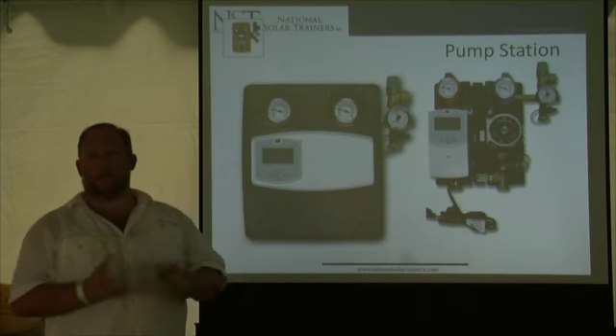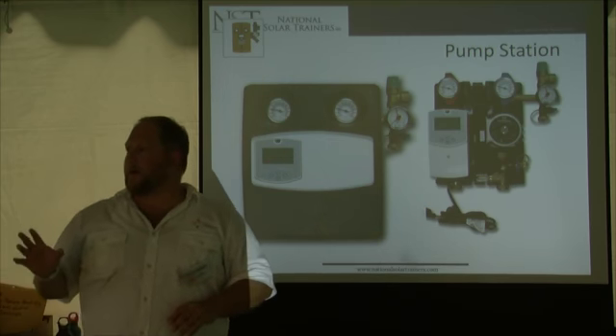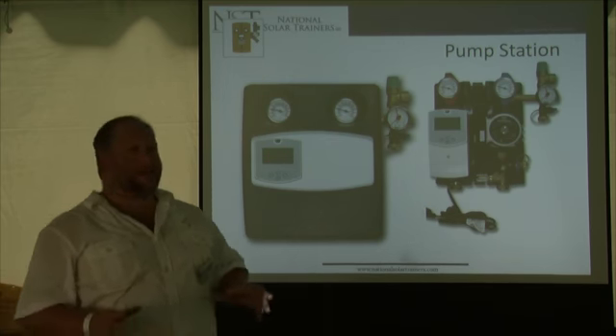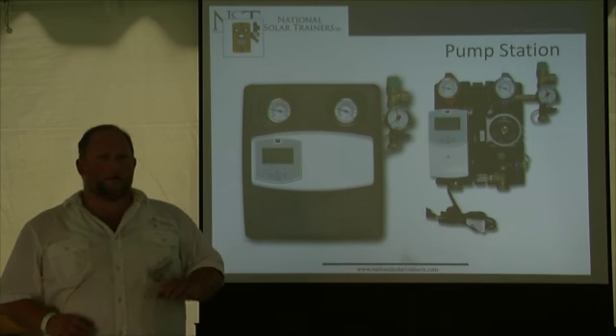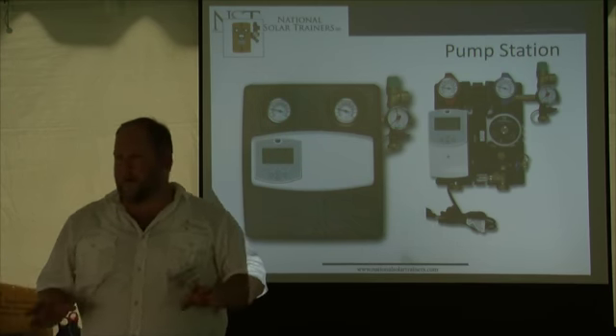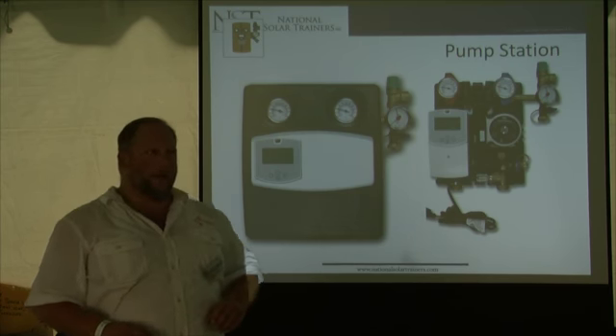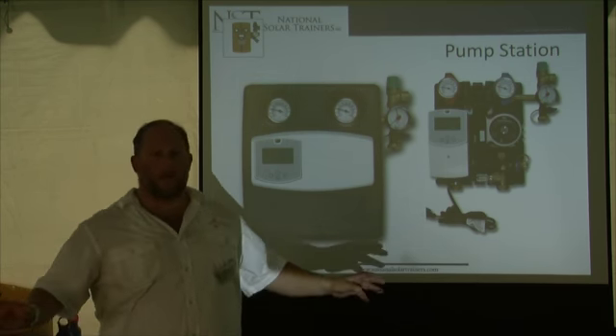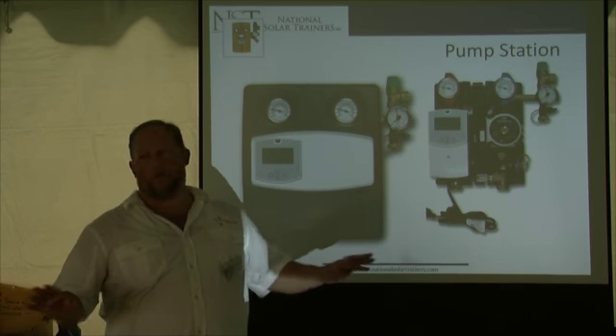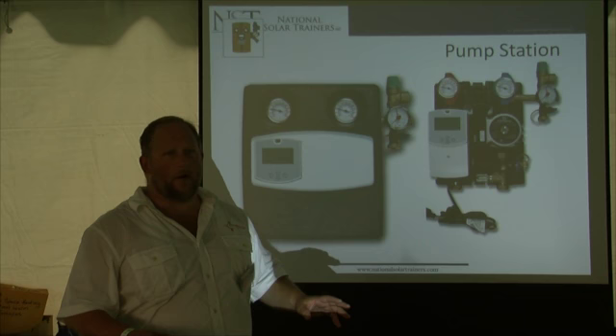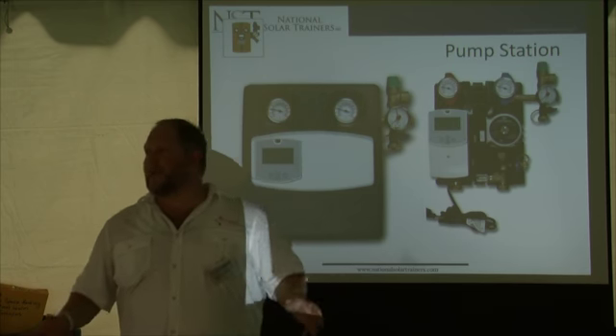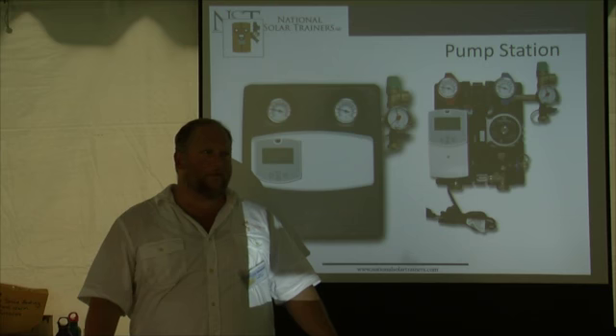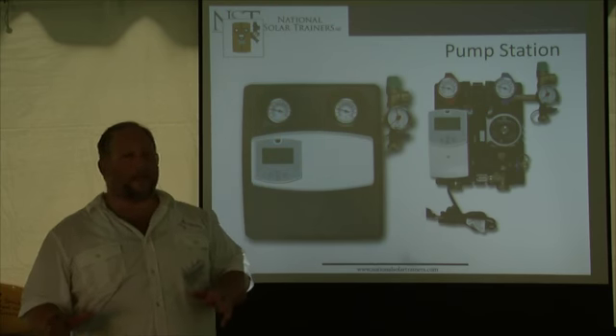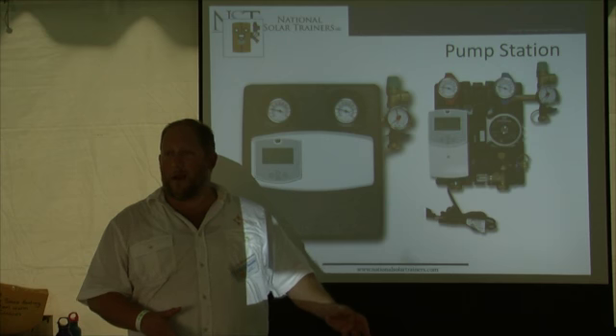Because when the collectors overheat, another very common misconception is that collectors can't overheat. They're designed to overheat. It's okay for them to overheat. I hear people say, oh no, the collectors are overheated. They burned. We have to replace them. No. That's what SRCC tests for. It's called stagnation. They're designed to handle 350, 450 degrees. That's not the issue. The issue is the glycol overheating.